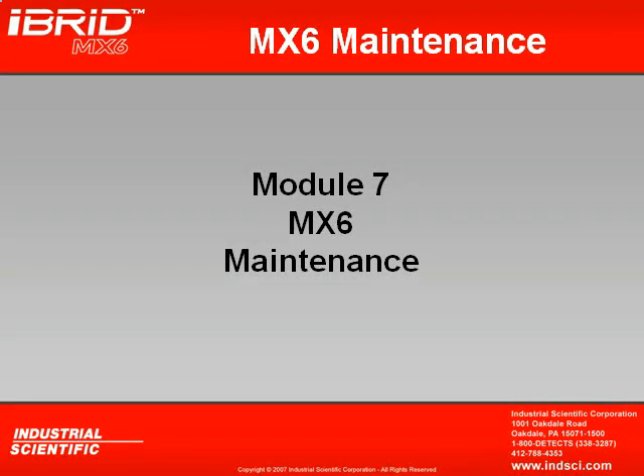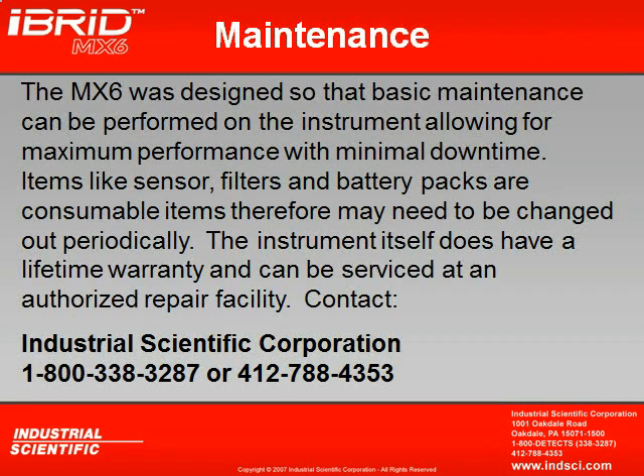In Module 7, we're going to cover the MX6 maintenance. The MX6 was designed so that basic maintenance can be performed on the instrument, allowing for maximum performance with minimal downtime. Items like sensors, filters, and battery packs are consumable items and therefore may need to be changed out periodically. The instrument itself does have a lifetime warranty and can be serviced at an authorized repair facility.